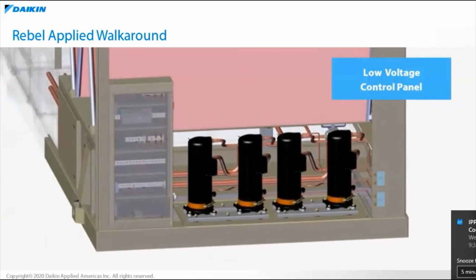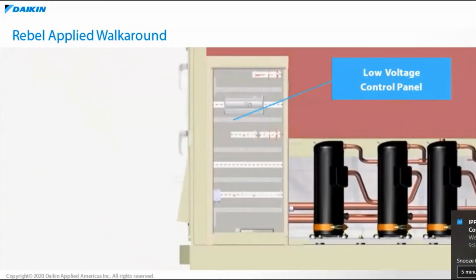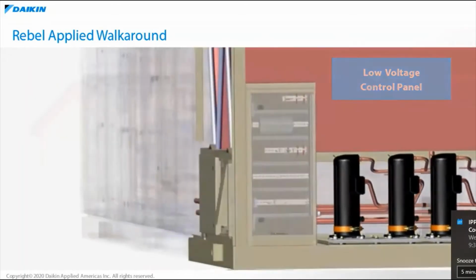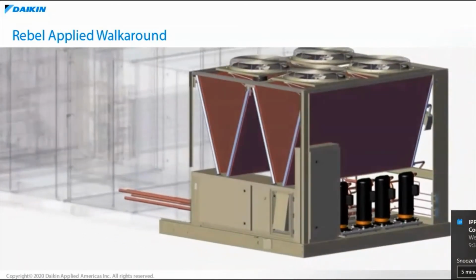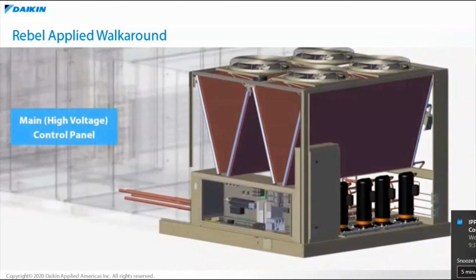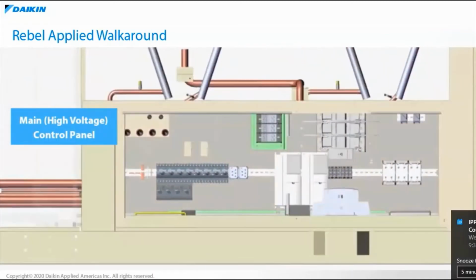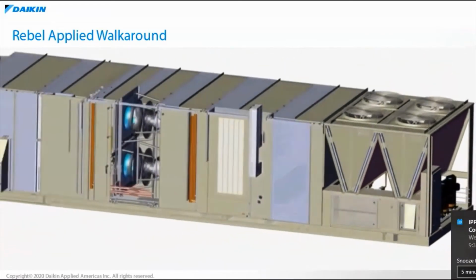The low voltage panel houses unit controls and is located on the end of the unit and provides safer access to low voltage components. The main or high voltage control panel is located low on the control side of the unit and includes standard and optional high voltage components such as disconnects, power blocks, electrical contactors, and others.